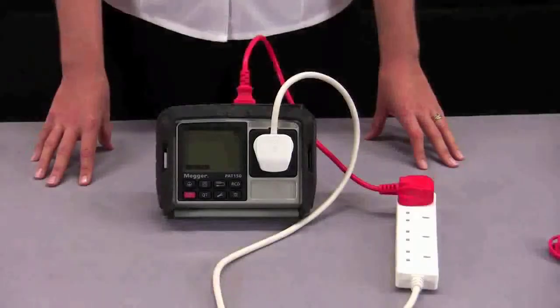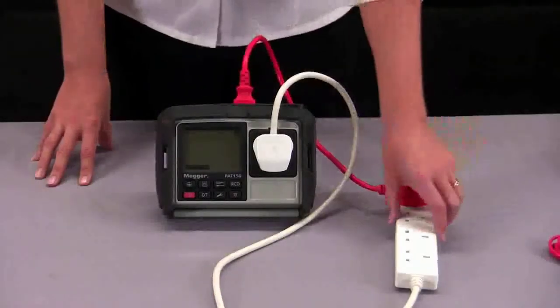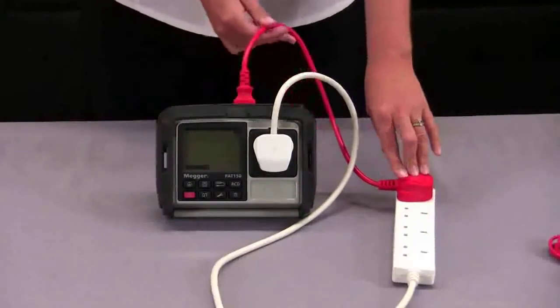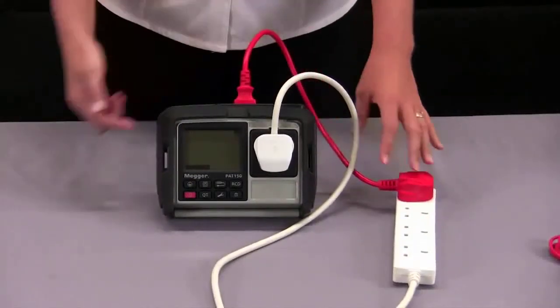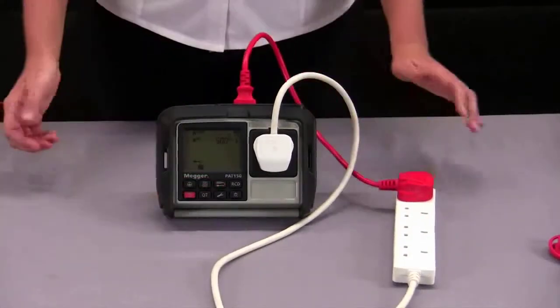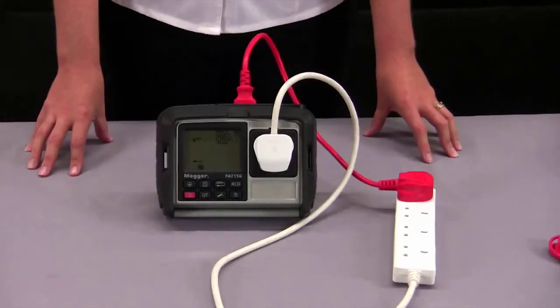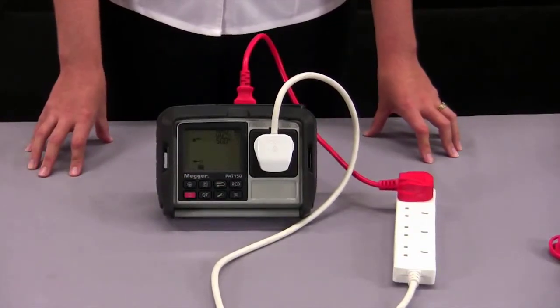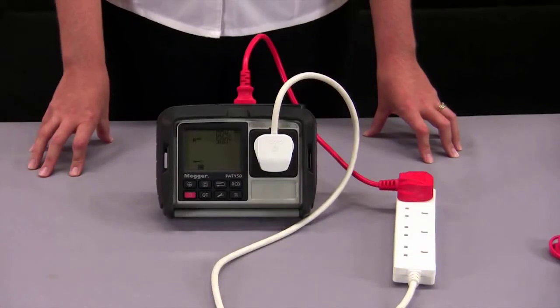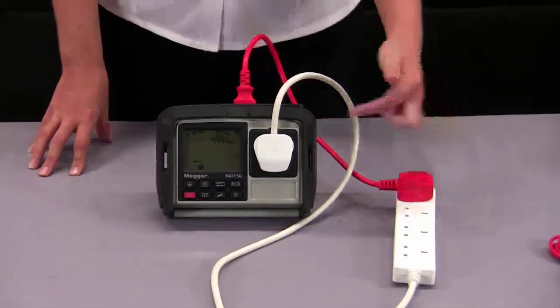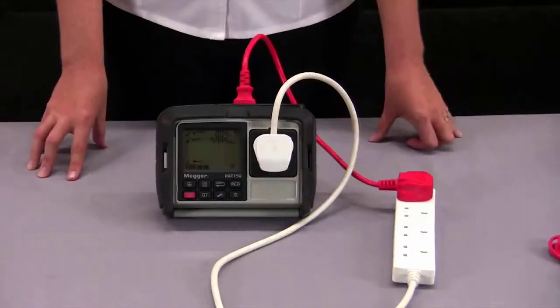Moving on to extension leads, I've got my lead plugged in, linked back to my tester using the red IEC lead. I can press the extension lead button to start the test. It will perform an earth continuity test, followed by insulation resistance. I have set to 500 volts, but for surge protected leads you might want to select 250 volts. It will then indicate the polarity is correct, and my pass or fail will be indicated on the right hand side.